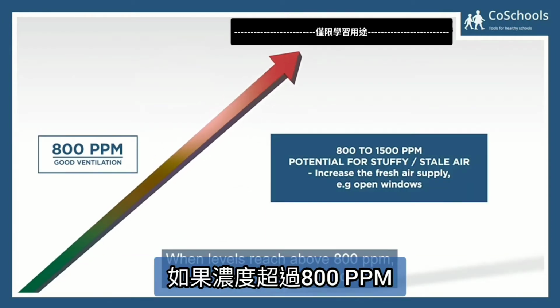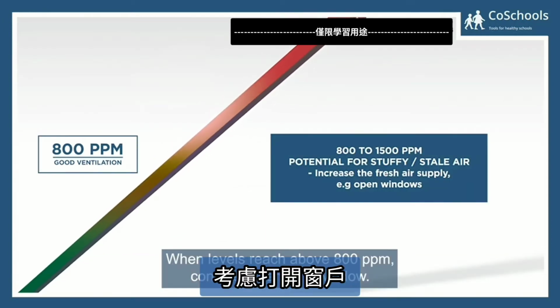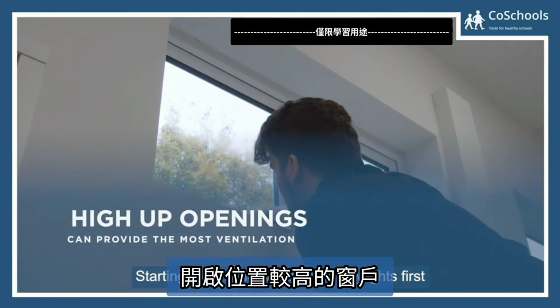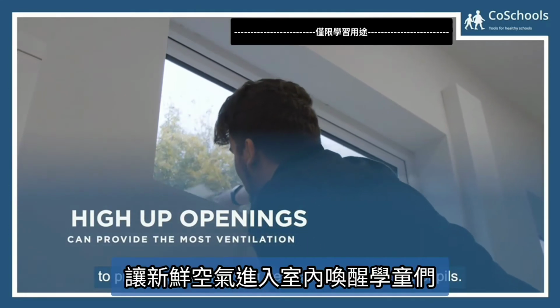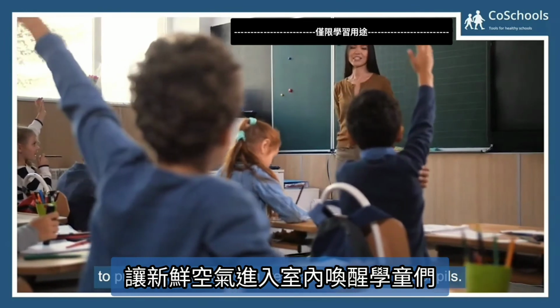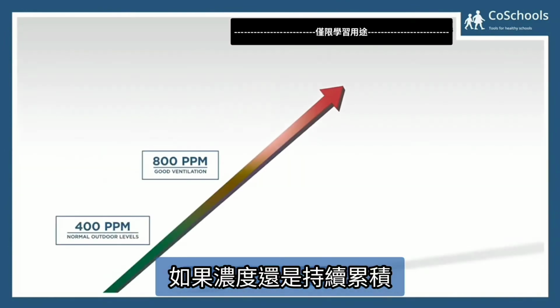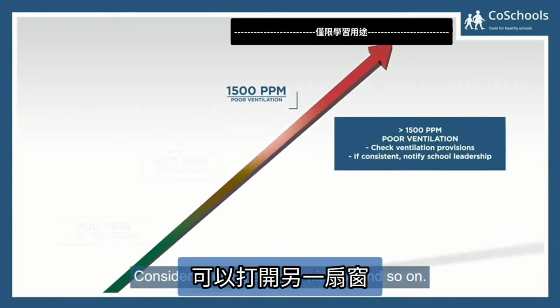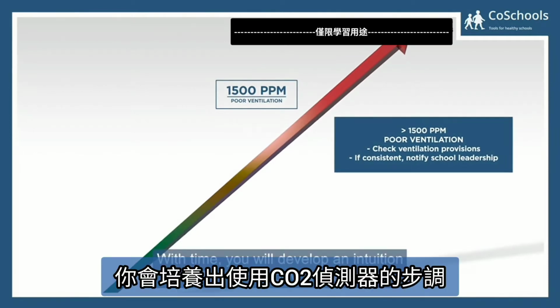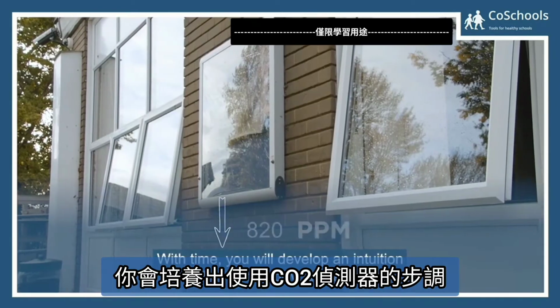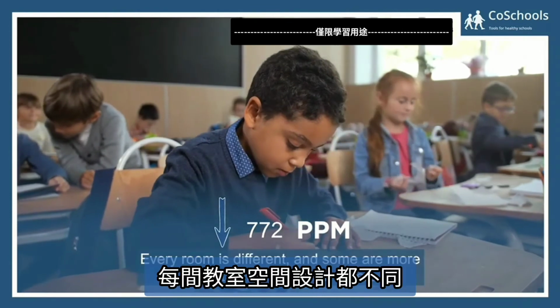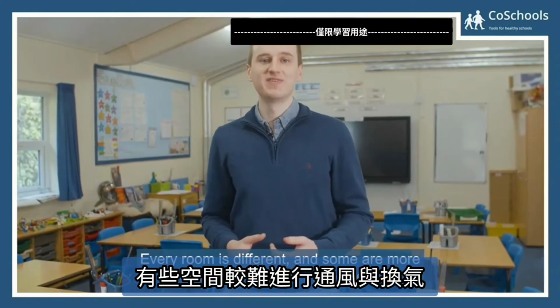When levels reach above 800 ppm, consider opening a window, starting with high-up windows or skylights first, to provide some relieving fresh air to wake up the pupils. If levels continue to increase, consider opening another window, and so on. With time, you will develop an intuition for what works for your classroom to consistently keep levels low. Every room is different, and some are more difficult to ventilate than others.